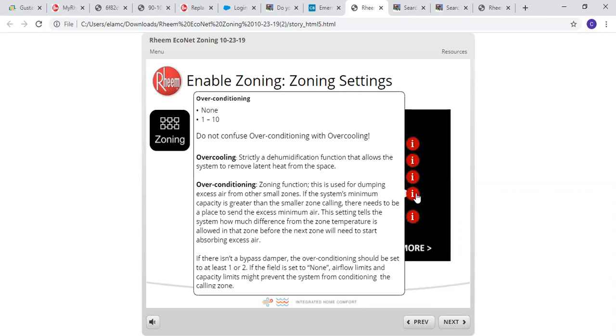You do have the ability to overcondition. So no overconditioning or 1 to 10 degrees. Do not confuse overconditioning with overcooling. Overcooling is strictly a dehumidification function that allows the system to remove latent heat from the space. Overconditioning, the zoning function, is used for dumping excess air from other small zones.